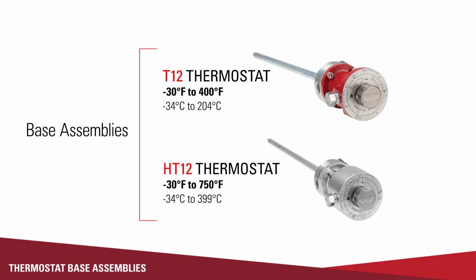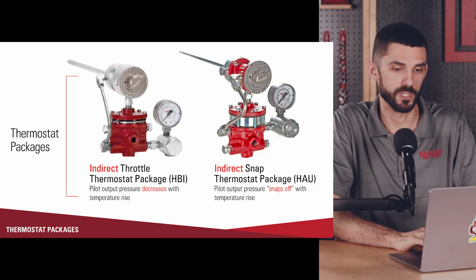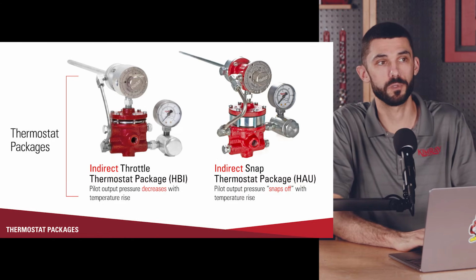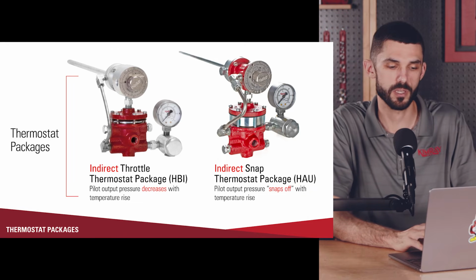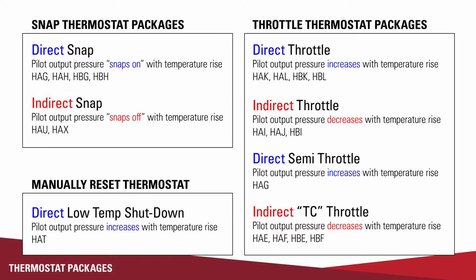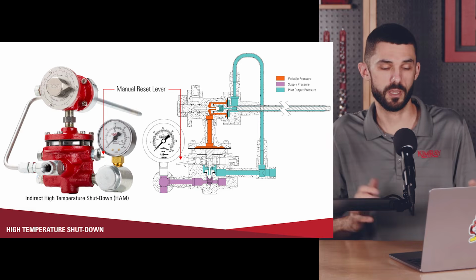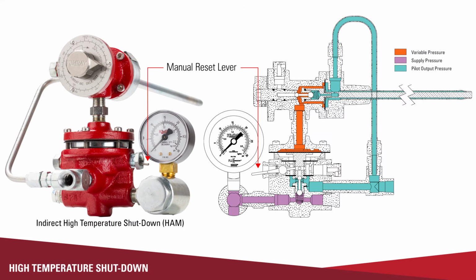So the T12 can operate from negative 30 degrees all the way up to 400 degrees. The HT12 can operate from negative 30 degrees up to 750 degrees Fahrenheit. As I mentioned before, the HT12 is normally used for high temperature shutdown applications. It's paired with a pilot, a manual reset pilot. So the high temp shutdown that I was speaking about, it's our part number HAM, but it's an indirect high temperature shutdown. So as you can see here, it'll be paired with a manual reset pilot.